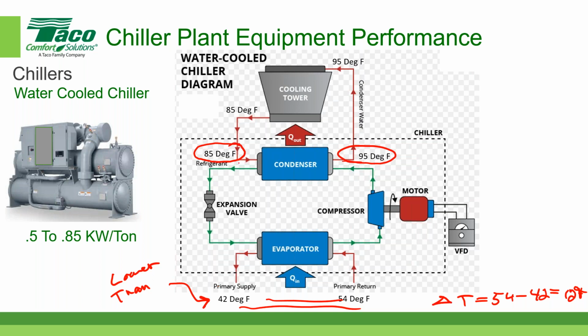And in order for heat transfer to take place, the refrigerant has to be leaving the condenser at above 85 degrees Fahrenheit. And we're going to see what those temperatures might be. They don't have to be these exact temperatures. It all depends on how the chiller manufacturer builds this chiller.